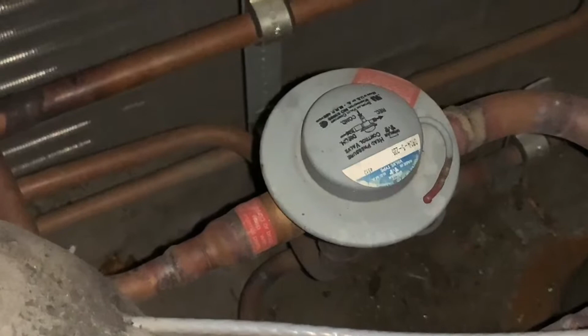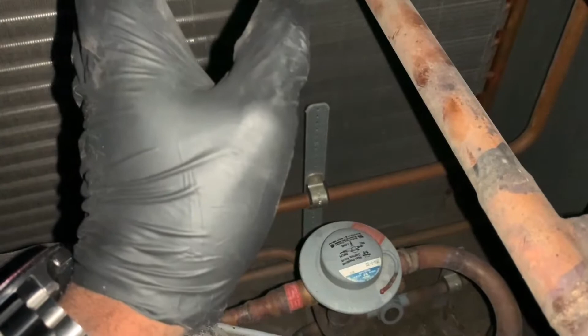So basically what this does, it will restrict the flow of refrigerant on the condenser, right? So it's restricting the liquid. It holds the liquid in the condenser, right? So when it's cold outside, when the ambient temperature is cold enough so that the head pressure is low, then it will restrict the flow of liquid through the condenser. So it holds the liquid in the condenser, and by doing that, you're building pressure simultaneously while it's holding the liquid. It's allowing some of the discharge gas to pass through and bypass the condenser.